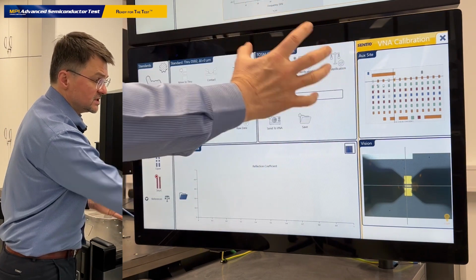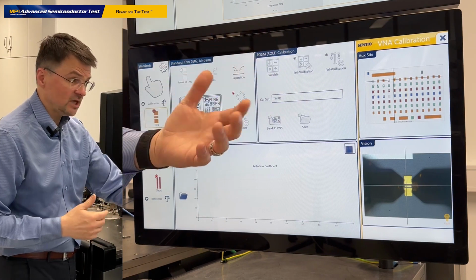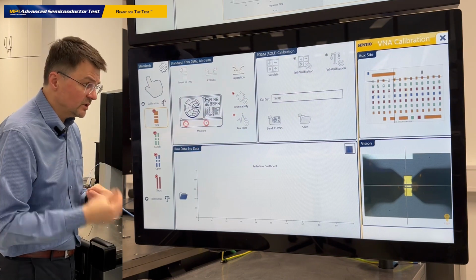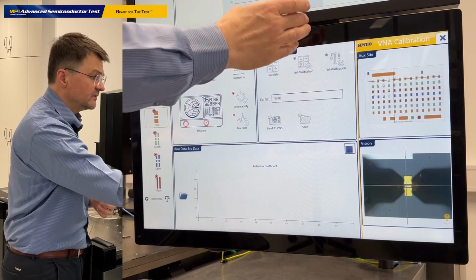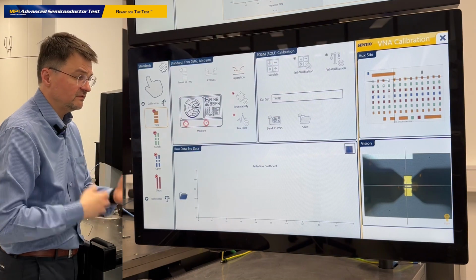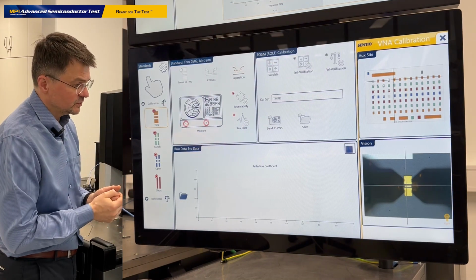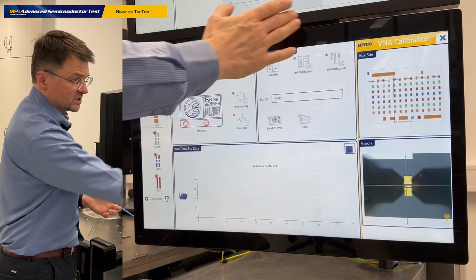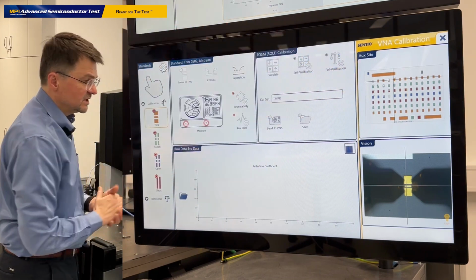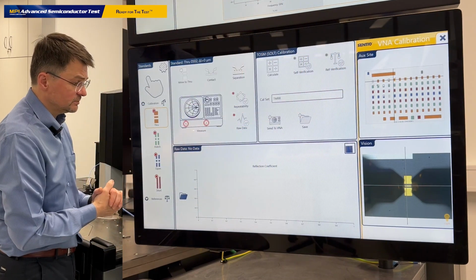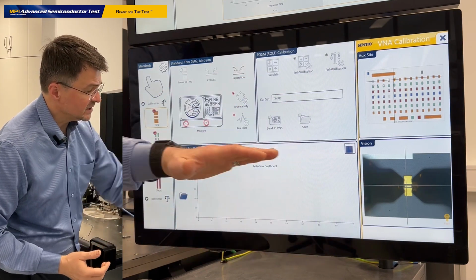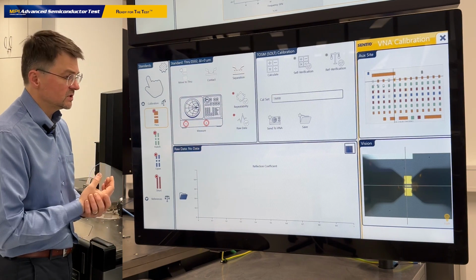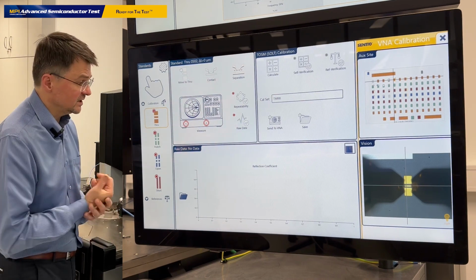This is the widget which we use to compute error terms in the manual mode, and verify the accuracy of the calibration process, both qualitatively and quantitatively. And we can back up the data and push the calibration error terms to the network analyzer. This is what is available from this particular widget, which is responsible for controlling the calibration process. And at the very bottom, we have a monitor for the different types of data associated with the measurement of the calibration standard and verifying the calibration process.